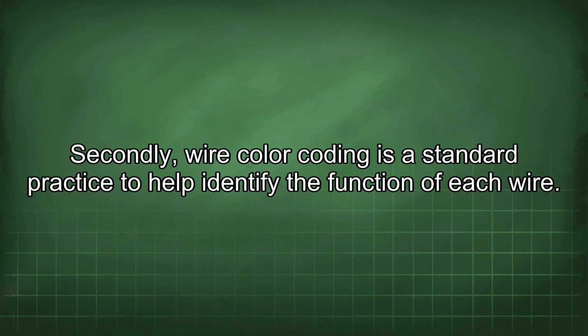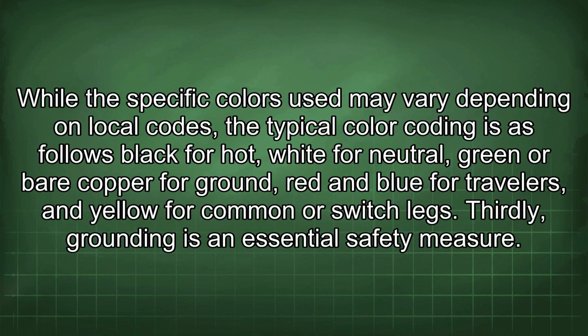Secondly, wire color coding is a standard practice to help identify the function of each wire. While the specific colors used may vary depending on local codes, the typical color coding is as follows: black for hot, white for neutral, green or bare copper for ground, red and blue for travelers, and yellow for common or switch legs.